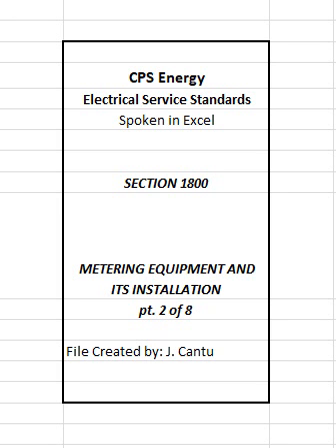G. Location of instrument transformers and enclosures. 1. 1 meter installations. A. For overhead service drops, donut-type CT/VTs will be furnished and installed by CPS Energy on a transformer mounting bracket, TMB, mounted on a service mast, meter pole, or on the building or structure. Where they must be installed on building wall or structure, customer shall install TMBs for CPS Energy.